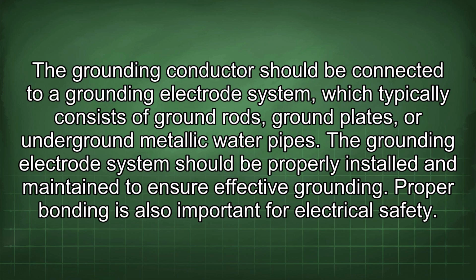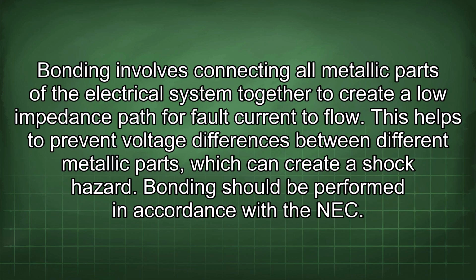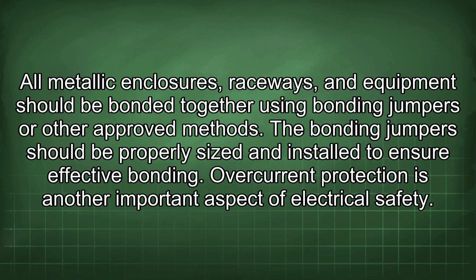Proper bonding is also important for electrical safety. Bonding involves connecting all metallic parts of the electrical system together to create a low impedance path for fault current to flow. This helps to prevent voltage differences between different metallic parts, which can create a shock hazard. Bonding should be performed in accordance with the NEC. All metallic enclosures, raceways, and equipment should be bonded together using bonding jumpers or other approved methods. The bonding jumpers should be properly sized and installed to ensure effective bonding.